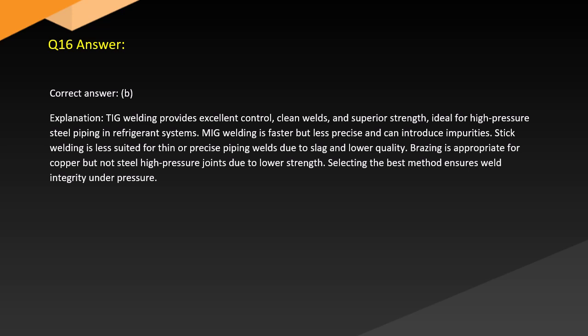Answer. Correct answer: B. Explanation. TIG welding provides excellent control, clean welds, and superior strength. Ideal for high-pressure steel piping in refrigerant systems. MIG welding is faster but less precise and can introduce impurities. Stick welding is less suited for thin or precise piping welds due to slag and lower quality. Brazing is appropriate for copper but not steel high-pressure joints due to lower strength. Selecting the best method ensures integrity under pressure.